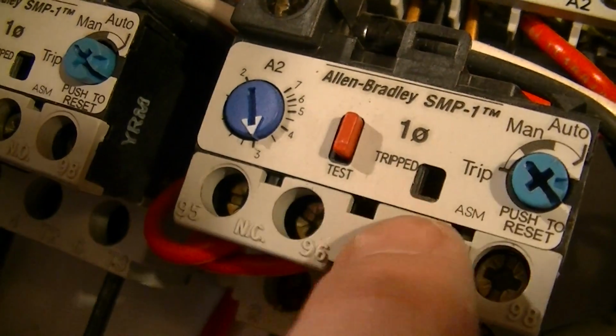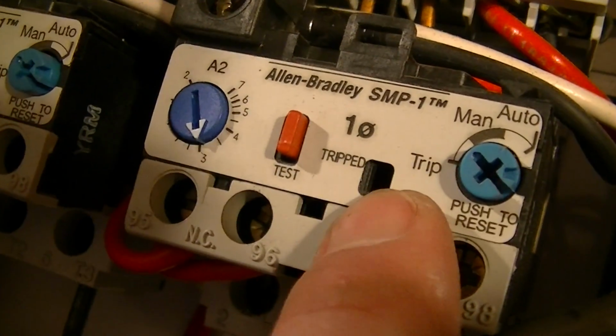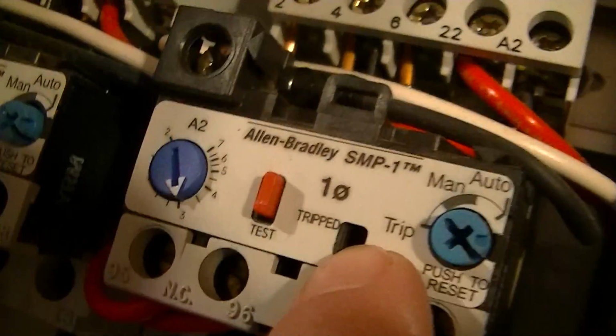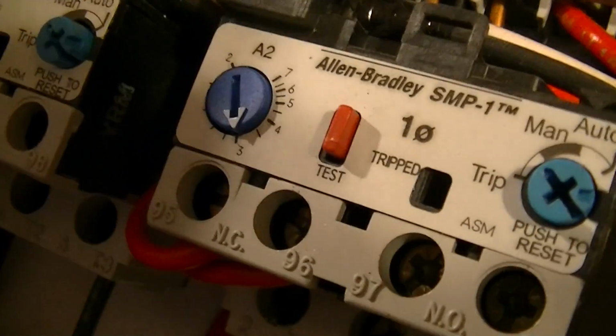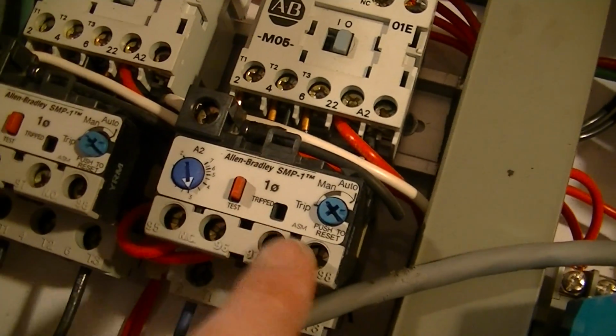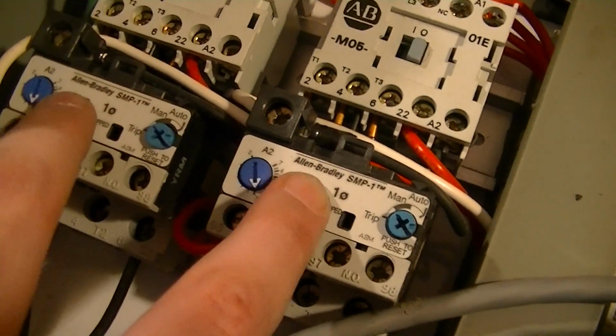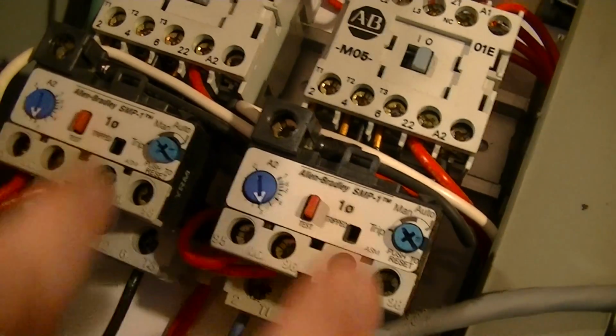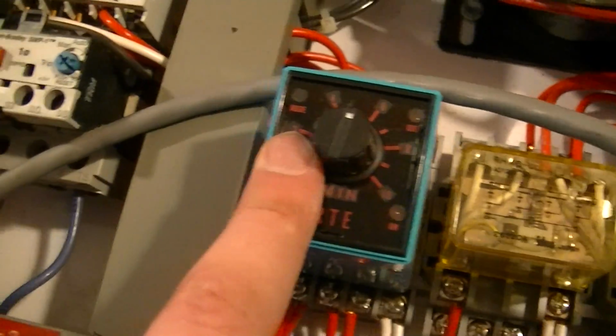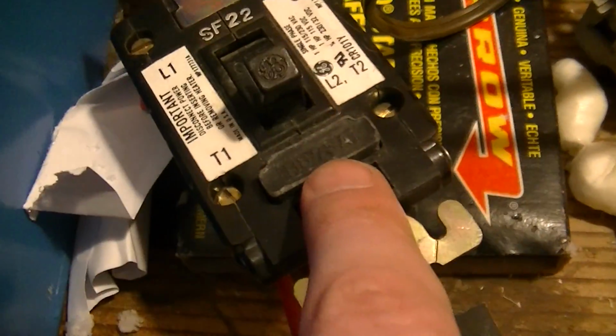And of course it's mechanically indicated because there's nothing to burn out like an incandescent lamp or an LED, which can fail, especially in industrial control stuff where you got all kinds of transients and nasty schmoo on the lines. Also, it's almost like an electrically actuated trip thing, just for testing the functionality of the electronics inside it, whereas more conventional motor starters have replaceable heaters.